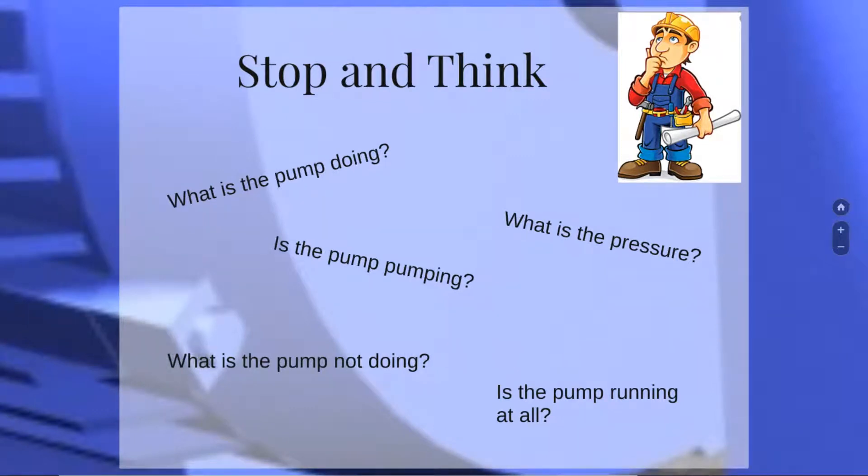Sometimes when I send someone to go take a look at a pump, the first thing I always ask them is: what is the pump not doing, what is the pump doing, what is the suction pressure, and what is the discharge pressure? Is the pump running at all? Pumps are what we call constant-head devices, and as a cast-and-head device, this pump is going to move fluid so fast, so high, and so far.